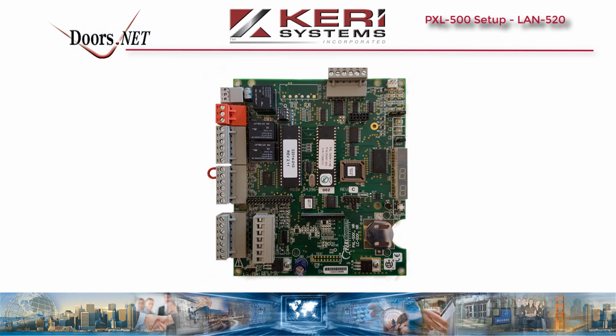You must now connect the LAN 520 module to the TB13 connector of the master PXL. The master is the controller addressed as number 1. The LAN 520 should be mounted with the Ethernet port and the LEDs on the right hand side of the PXL PCB. On the PXL there are also two jumpers labelled JP6 and JP7. These jumpers both need to be removed to correctly configure the PXL for Ethernet communications.